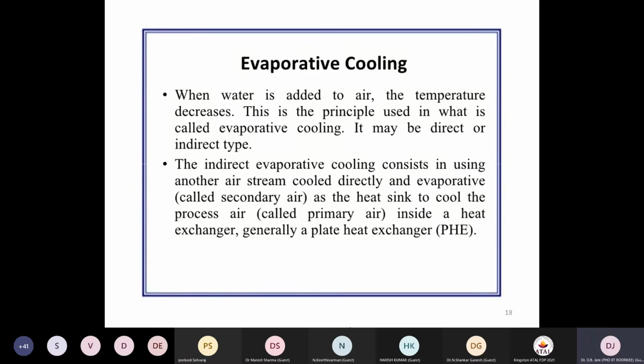The cooling process originates with the thermodynamics of evaporative cooling. Thermodynamically, evaporative cooling is an endothermic process. For water to evaporate below its saturation point, you have to provide a certain amount of heat so that the water may evaporate, and during evaporation it extracts heat from its surroundings, so the remaining air gets cooled. Certain water itself is also lost in the form of evaporation.